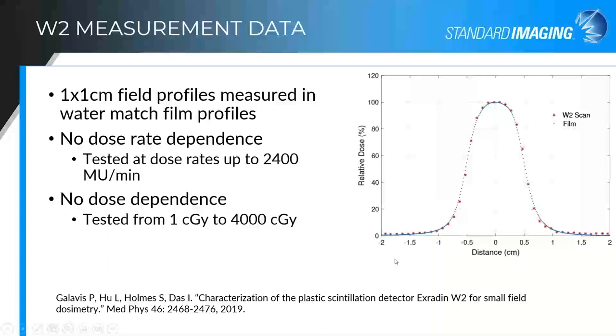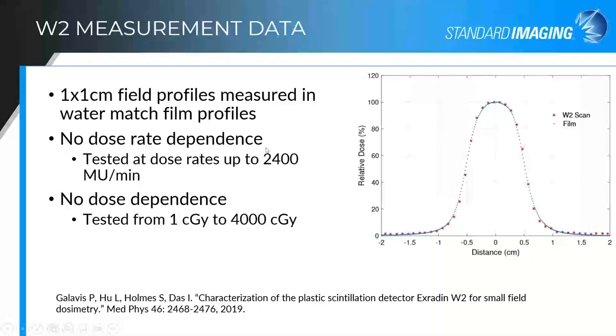From an early publication on the W2, a comparison was done between water tank scanning and GAF chromic film measurements for a 1 cm field. The W2 measurements showed excellent agreement with the film scan. They also verified that, just as with the W1, there were no dose rate dependencies seen up to 2,400 MU per minute and no dose dependencies seen from 1 cGy to 4,000 cGy.